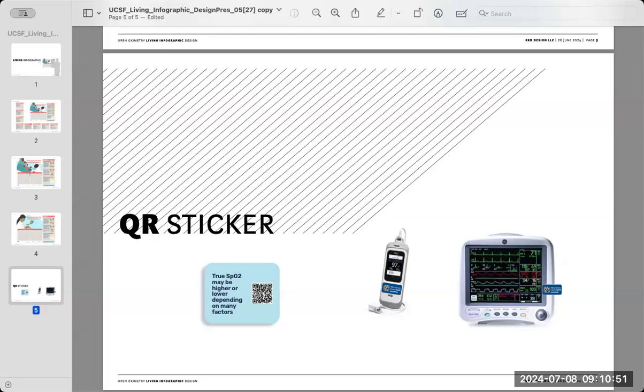And it is the reference for which manufacturers claim to benchmark their accuracy. So I don't think we're going to find a lot of people drawing blood gases. Right. And so that's why that QR sticker needs to declare the manufacturer's accuracy performance against a blood SAO2 value.